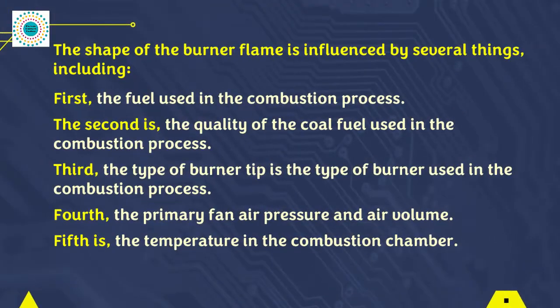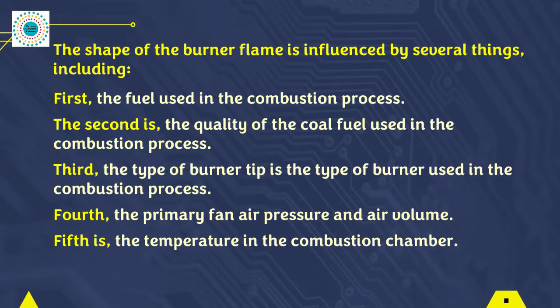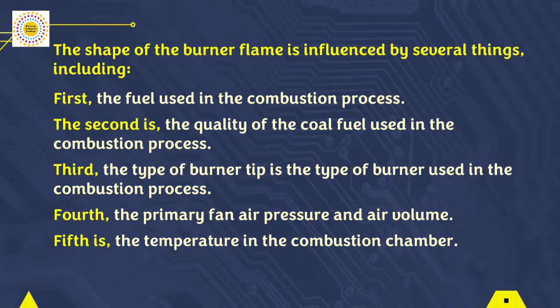The shape of the burner flame is influenced by several things, including: first, the fuel used in the combustion process; second, the quality of the coal fuel used in the combustion process; third, the type of burner tip used in the combustion process; fourth, air pressure and air volume from the primary fan; and fifth, the temperature in the combustion chamber.